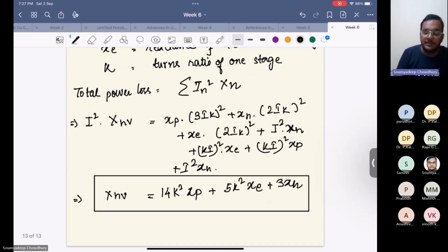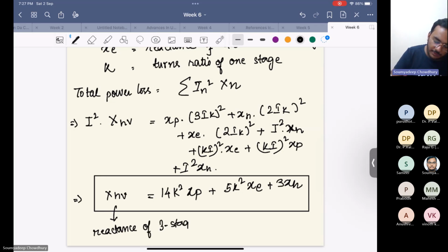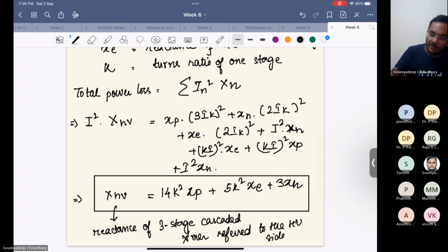Is it clear? So this is the reactance of a three-stage cascaded transformer referred to the HV winding. This we have done referring to the HV side. If we were to refer it to the primary side, we have to refer all the windings and all the currents to the primary side. Is it clear?